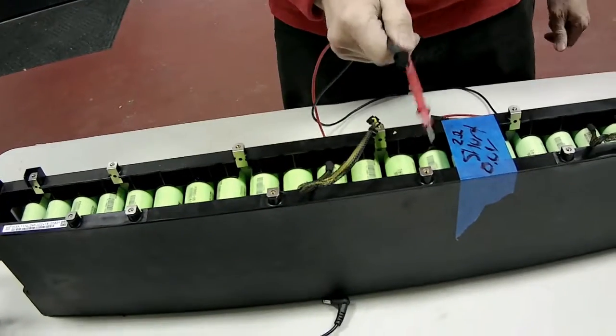If one electrode on this pack touched one electrode on that pack, it would be okay. If two electrodes on this pack touched two electrodes on that pack, it could be an instant fire. You'd have thermal runaway. Or first, the flash might blind you, and then you wouldn't be able to see where the fire extinguisher was, or find where the controls are on the forklift to drive it out in the parking lot and dump it.